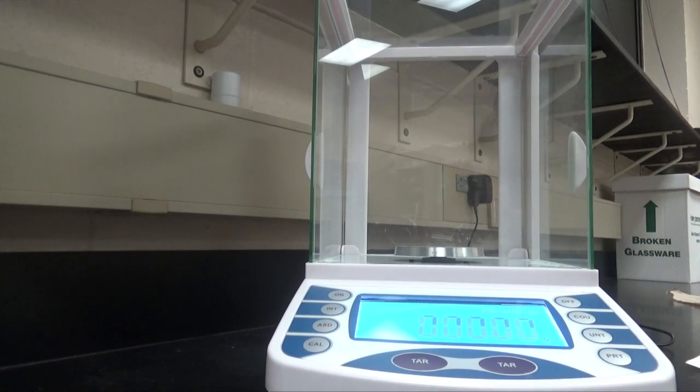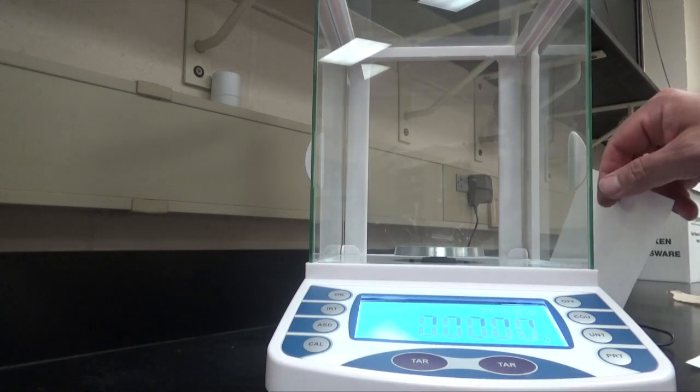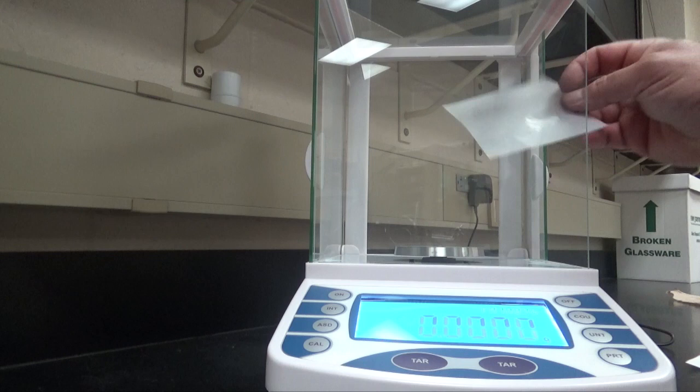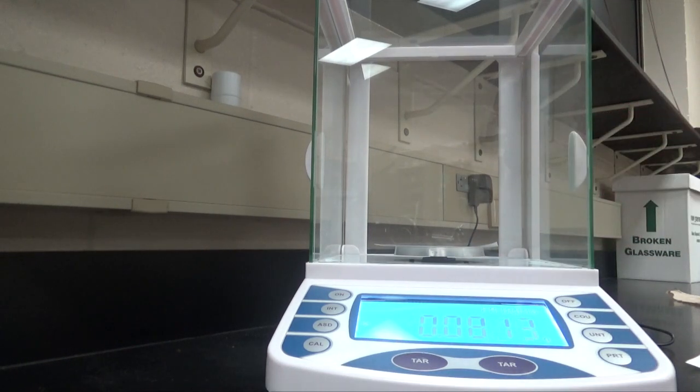When using an analytical balance, it's important that we place a piece of weighing paper. Now you'll notice that this is enclosed to prevent air currents. This balance will go to four decimal places, and so I'm going to place a piece of paper down and close this and press tare. Wait for it to pause. I'll press tare.